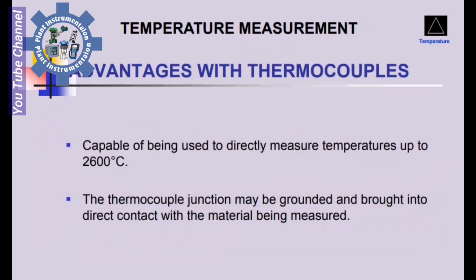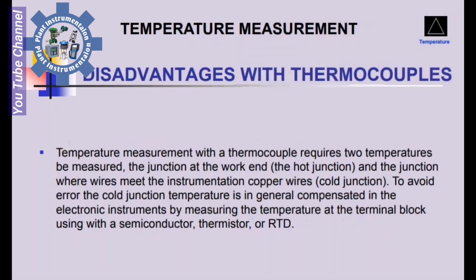Advantages of thermocouples. They are capable of being used to directly measure temperature up to 2600 degrees Celsius. The thermocouple junction may be grounded and brought into direct contact with the material being measured. Disadvantages of thermocouples. Temperature measurement with a thermocouple requires two temperatures to be measured: the junction at the work, the hot junction, and the junction where the wires meet the instrumentation copper wire, the cold junction. To avoid error, the cold junction temperature is in general compensated in the electronic instrument by measuring the temperature at the terminal block using a semiconductor, thermistor or RTD.